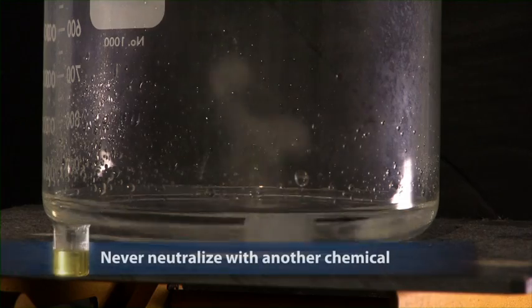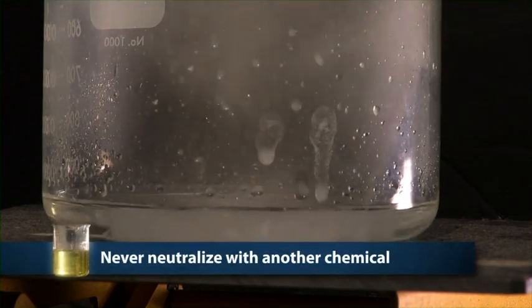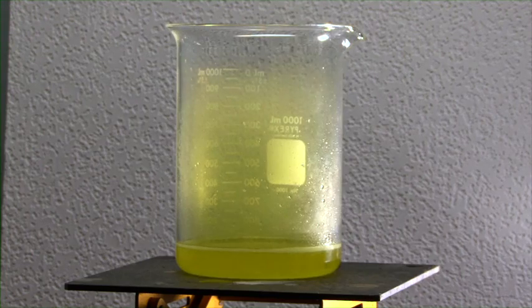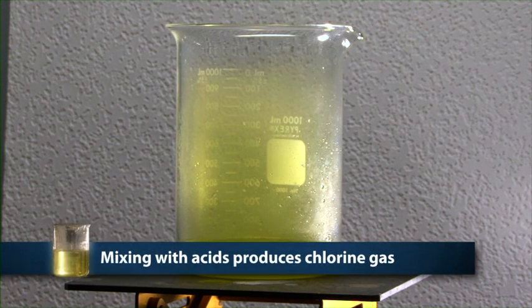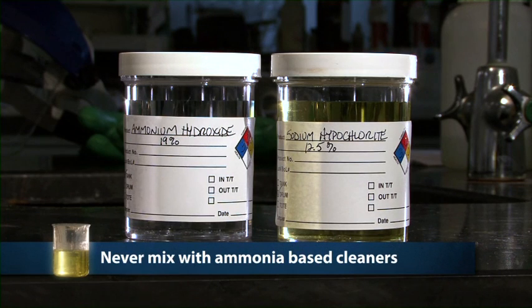Never attempt to neutralize the sodium hypochlorite with another chemical. Mixing sodium hypochlorite solutions with acids or acidic products can result in the release of toxic chlorine gas. Never mix ammonia solutions or ammonia-based cleaners with bleach or with products containing bleach. The mixture quickly produces hazardous vapors.